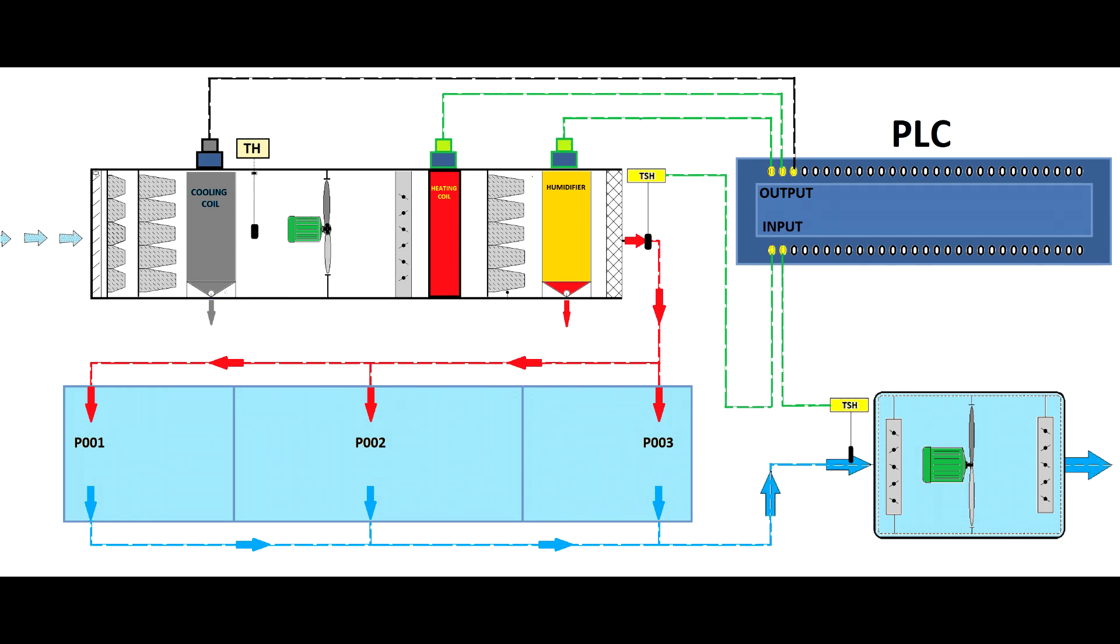And all that air will pass by through the AHU, will pass the sensors onto the air flow, will go into the room, and then will be extracted. And at that point, that sensor onto the extractor fan duct will pick up the fact that the temperature is too high or too low, or the air has too much or not enough humidity, and it will act very late. So because that probe instructs the PLC to act onto these actuators which control the heat exchangers, the trend will look very bad because the room moisture will be too high before this actuator to act and to allow the heat exchangers to do their job. Once the heat exchangers will start doing their job, maybe they'll dry the air too much or will cool the air too much or heat the air too much until that air will reach the extractor fan probe.